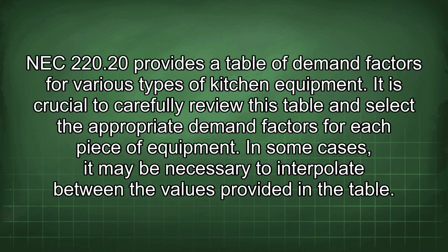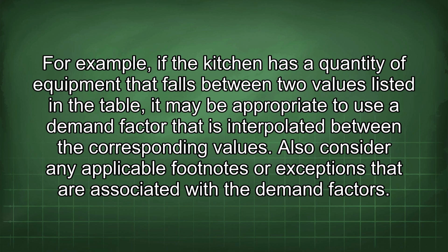It is crucial to carefully review this table and select the appropriate demand factors for each piece of equipment. In some cases, it may be necessary to interpolate between the values provided in the table. For example, if the kitchen has a quantity of equipment that falls between two values listed in the table, it may be appropriate to use a demand factor that is interpolated between the corresponding values.